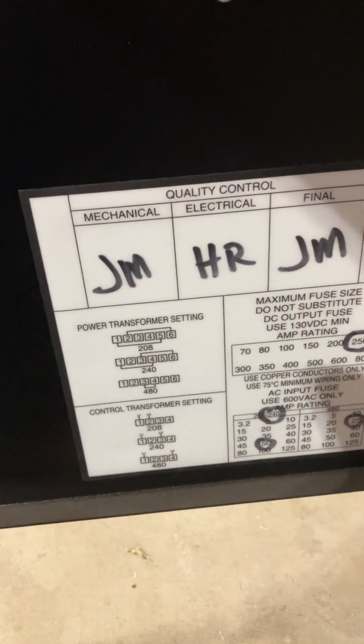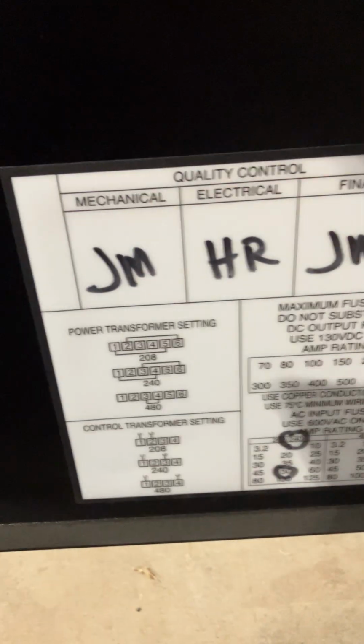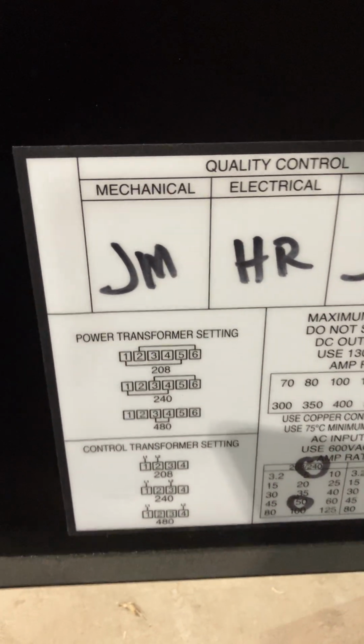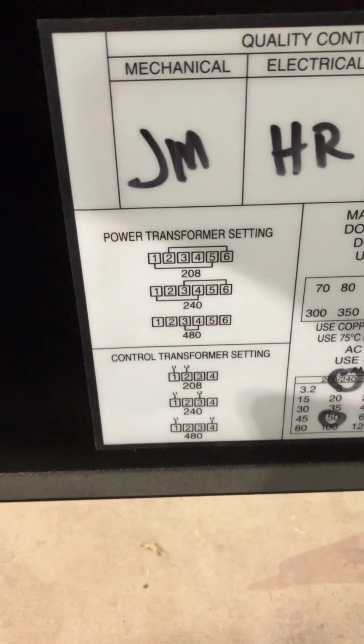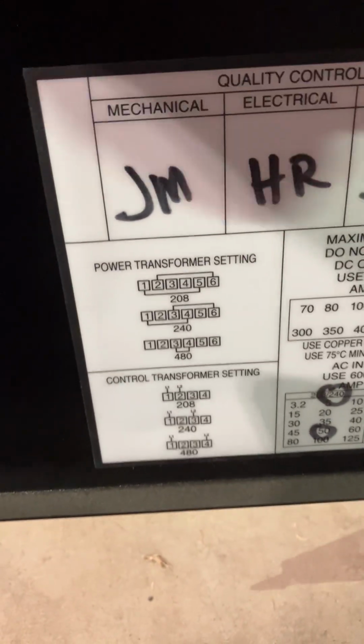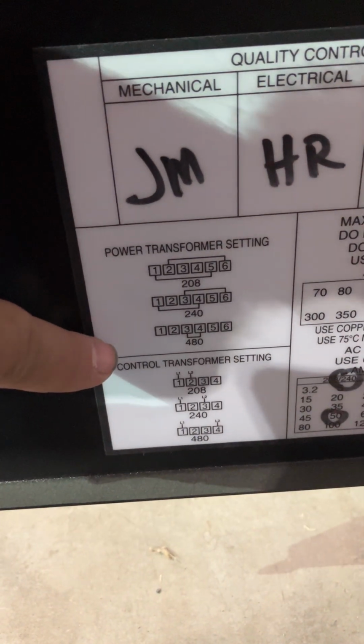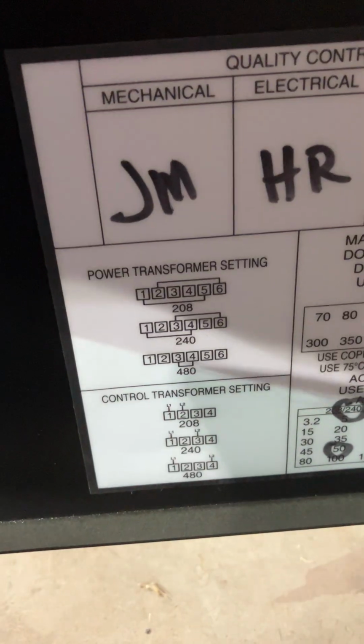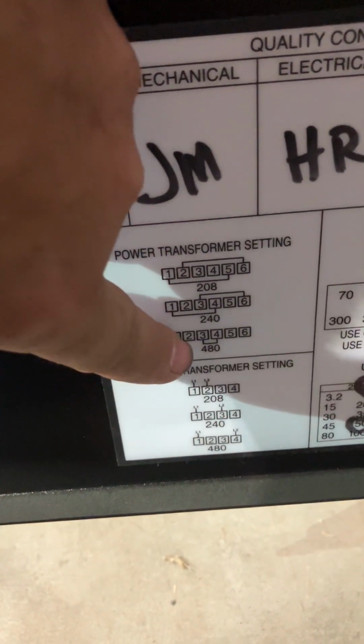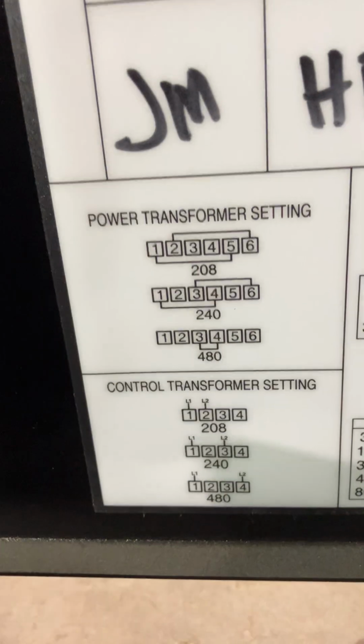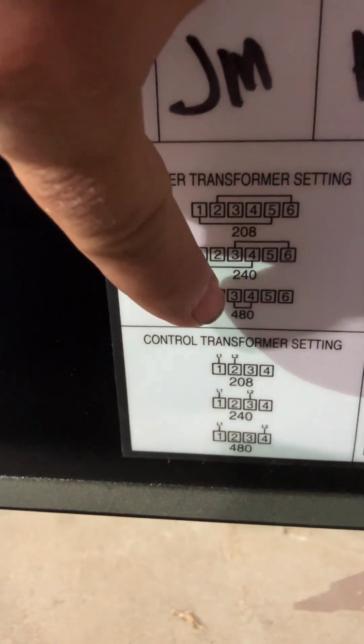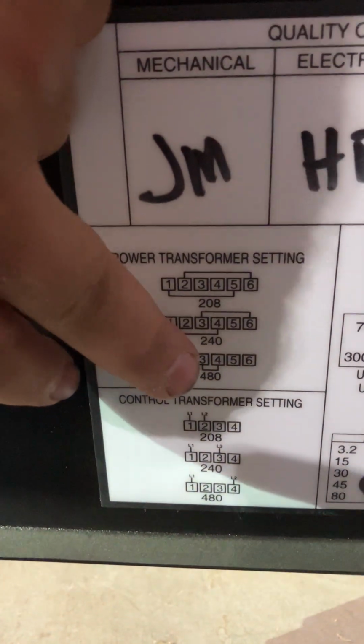Here's something to watch out for, and I didn't quite get it right at first. After 25 years in this trade, I still sometimes make a mistake. See that right down there? It says power transformer settings and control transformer settings. Make sure that both your power transformer and control transformer are set according to the voltage you're actually going to be feeding to it. You may feed 240 to it, right there in the middle. You may feed 208 to it, right there on top. Down at the bottom, you may be feeding, as we are in this case, 480 volts. You've got what are called shorting wires, and we're going to put the shorting wires between 3 and 4.